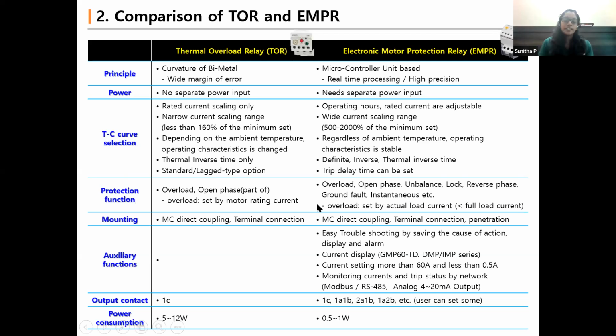Okay, so this is where I was mentioning thermal overload relay versus electronic overload relay. You have a wide span, and irrespective of ambient temperature the operating characteristics are stable. You can have definite, inverse, and thermal inverse time, and trip delays can be set. These are a few advantages over the thermal overload relay. In addition to the basic functionality, you can have inbuilt auxiliary functions, wherein you can get 1 NO, 1 NC, or up to 5 NC. At the same time, the power consumption is very low. So these are the advantages of electronic overload relays.